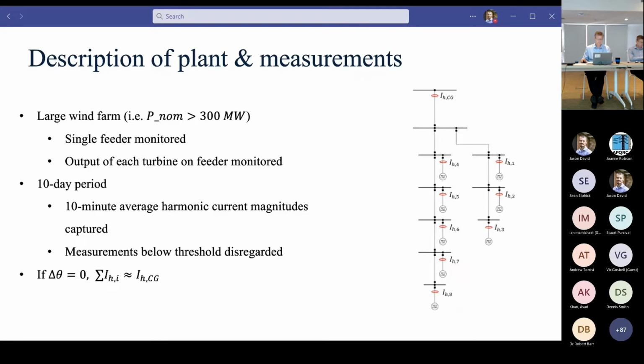We collected 10-minute average harmonic current magnitudes only, so we aren't looking at phase angles, we're simply looking at magnitudes. And also measurements below a measurement threshold were disregarded. I'll go into this in a little more detail because it has an important impact on the outcome. What we can say, and I kind of said it in the last slide, is that if there is very little change in the phase angle between each individual harmonic source, then the arithmetic summation of each individual measured current should be very close to the value that we actually measured through that collector cable.